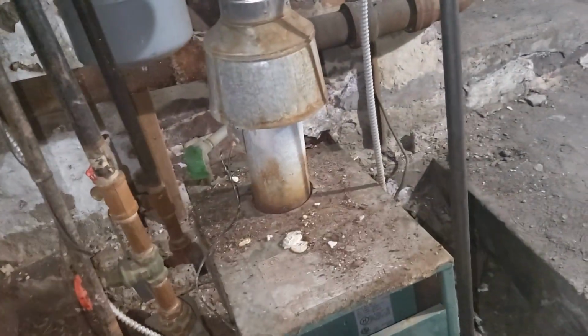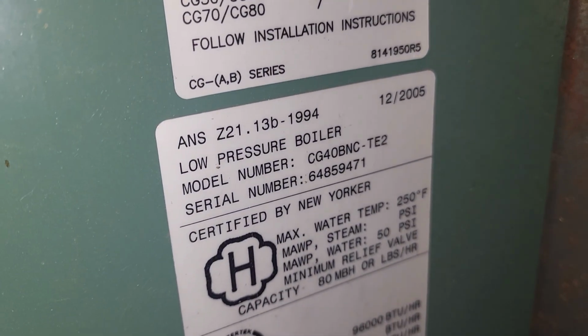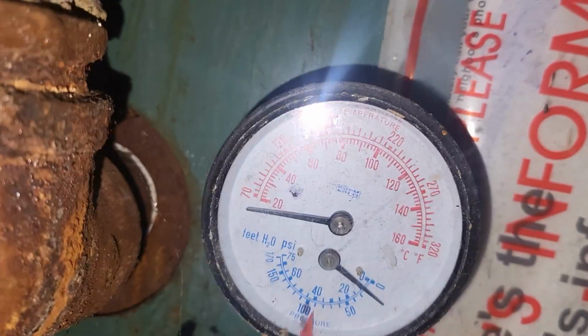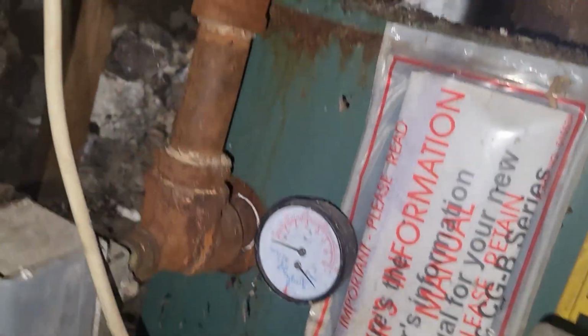Guys, this customer has 3 boilers. This second floor is the one that's not working. It's a New Yorker, 2005. Looks like our pilot light is on. Looks like it's a low water cutoff, which is not active, which is good.